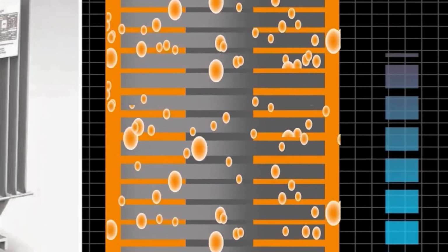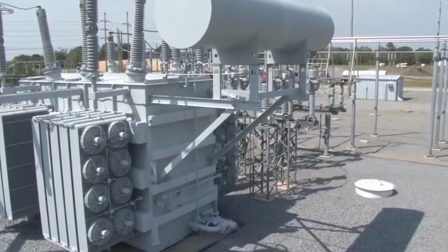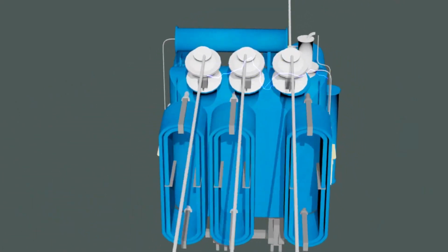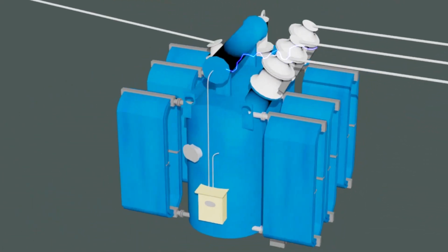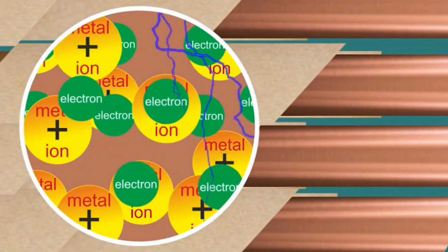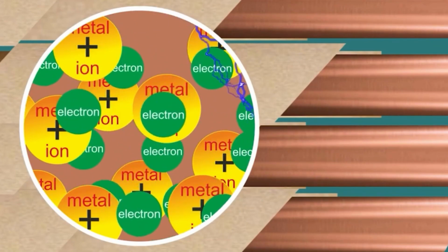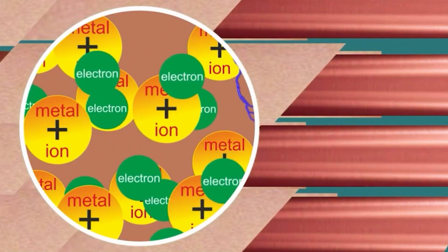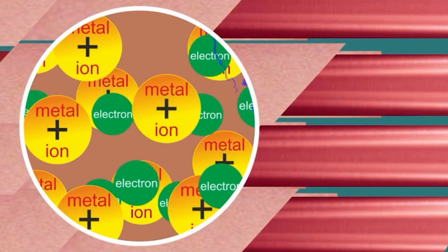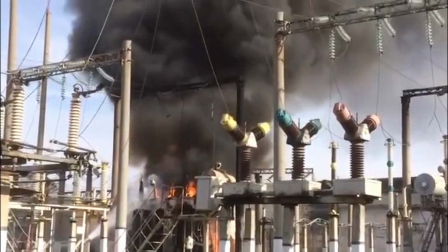The deterioration of dielectric characteristics leads to an increase in losses with higher than normal release of heat and, accordingly, to thermal breakdown and localized overheating of the insulation. Furthermore, moisture speeds up the processes of oxidation of transformer oil, thermal aging and degradation of cellulose, which leads to a decrease in the mechanical strength of paper insulation. Failure to maintain the moisture content within specified limits may result in transformer failure, power outages for consumers, and considerable financial losses for power distribution companies.